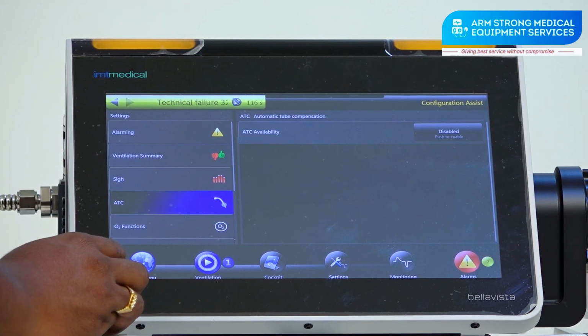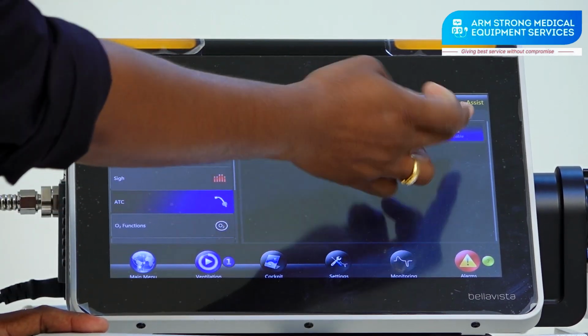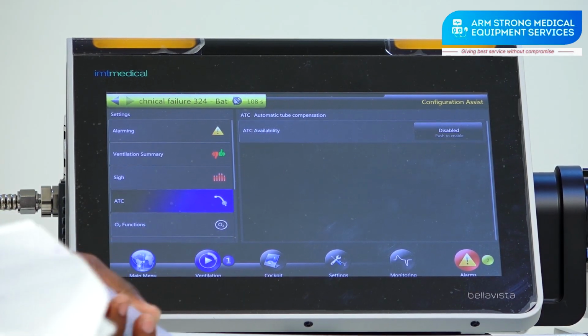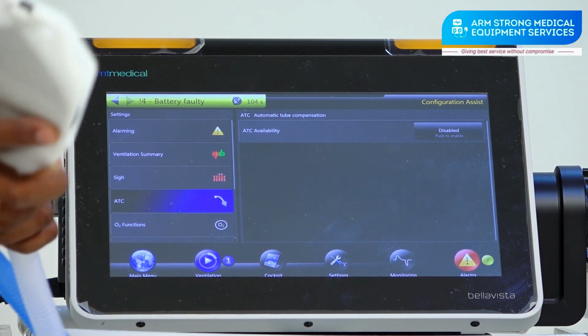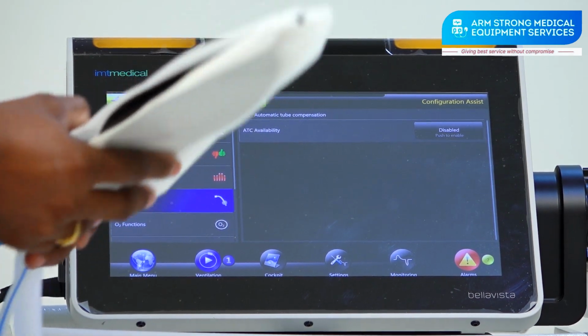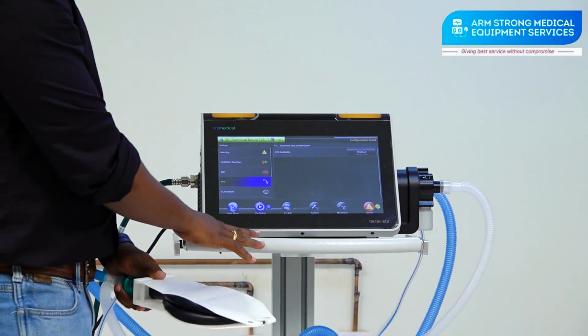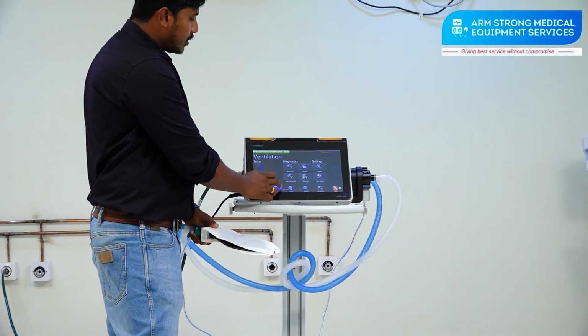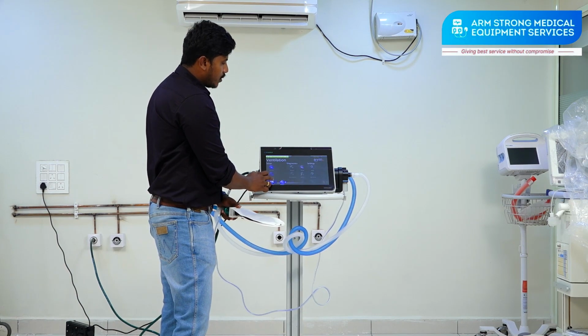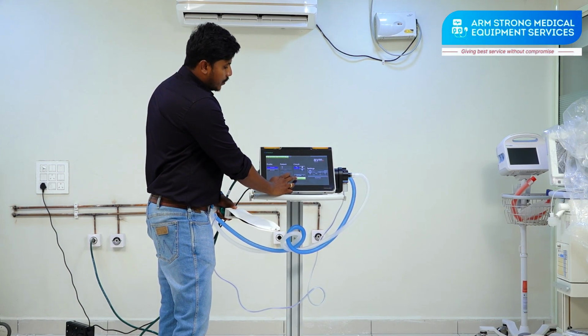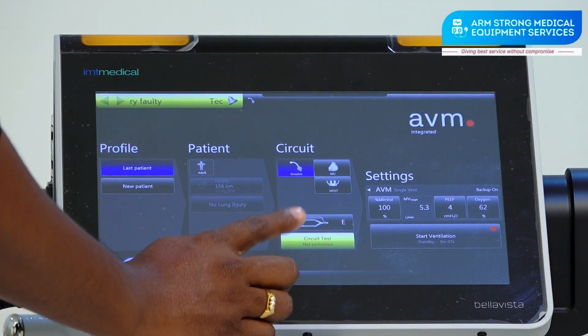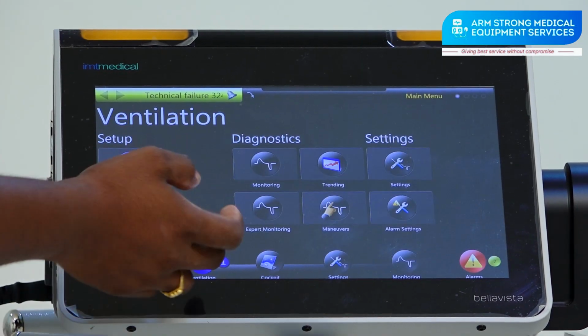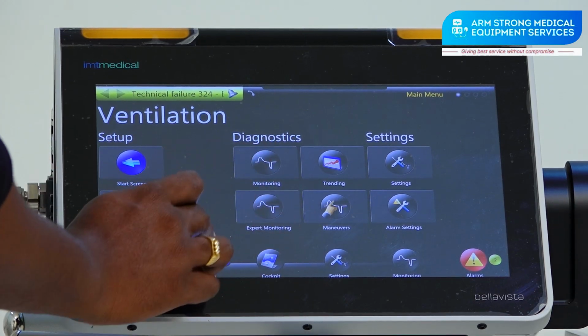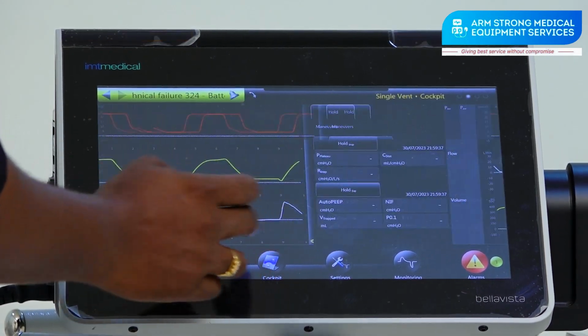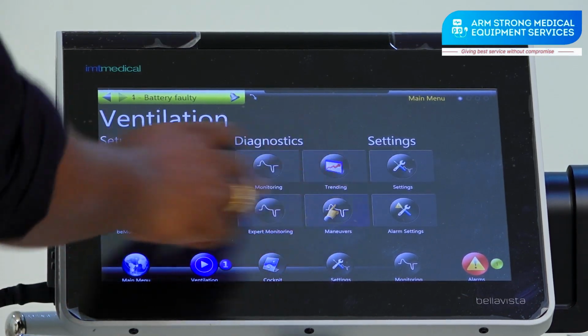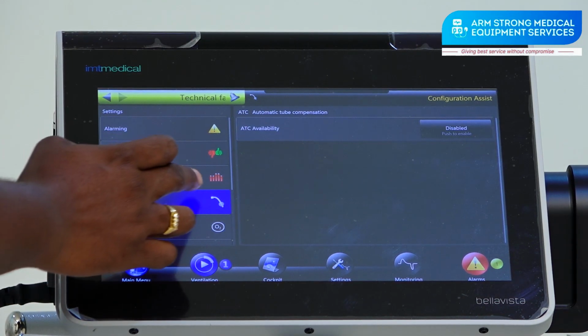So we have the automatic tube compensation also. You can enable or disable it, depending on whether you are using a pediatric patient circuit or an adult patient circuit. At that particular time, the ATC availability is very useful, automatic tube compensation. Why? Because whenever you check the circuit on the first page, the circuit test will be performed, and depending on that circuit test, the tube will be compensated. The ventilator will take that tube compensation. So if you have not done the circuit test and you enter this page and start ventilation, you can go to this configuration and just enable this ATC.